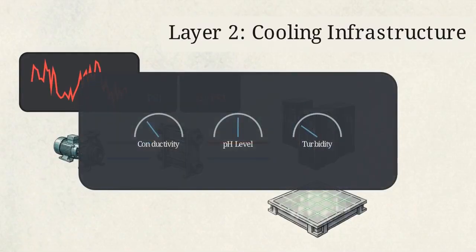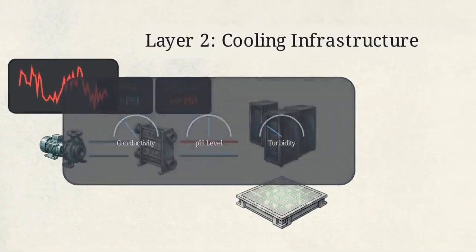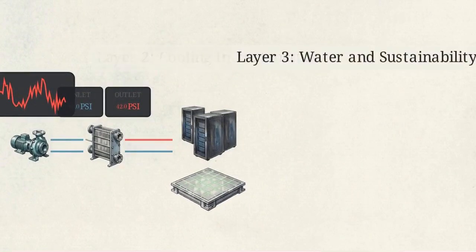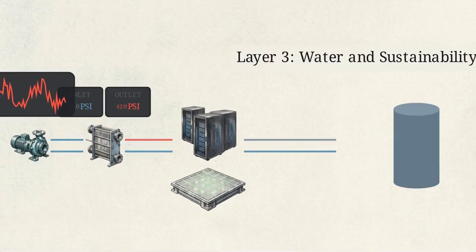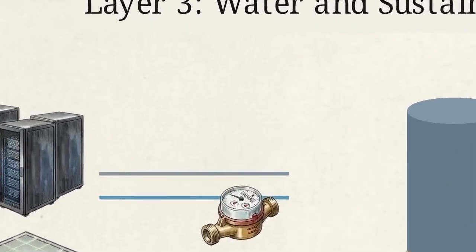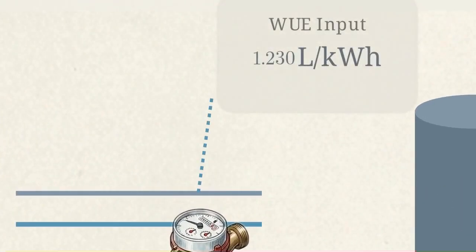These loops carry expensive fluids through sensitive metallic infrastructure. Measuring conductivity, pH, and turbidity ensures the chemical treatment is working and prevents severe internal corrosion. The cooling loops connect outward to Layer 3, water and sustainability. Dissipating the thermal load of an AI campus requires hundreds of thousands of gallons of water circulating between the internal mechanical plant and the external cooling towers.